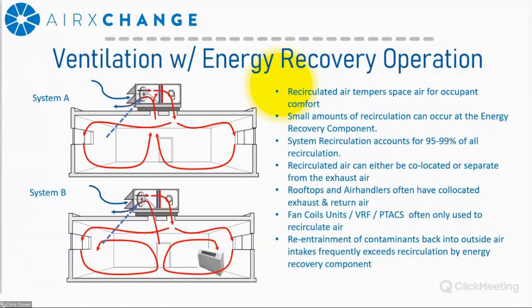So let me just put that. In what I just drew there, systems like rooftops and air handlers, like System A, often have co-located exhaust and return air streams and provide a mixed air stream consisting of both outside air and filtered recirculated air. Or you can have systems like System B. Systems like B would be examples such as fan coil units, VRF, PTACs, where one system is handling the outside air and one system is handling the recirculated air for occupant comfort.